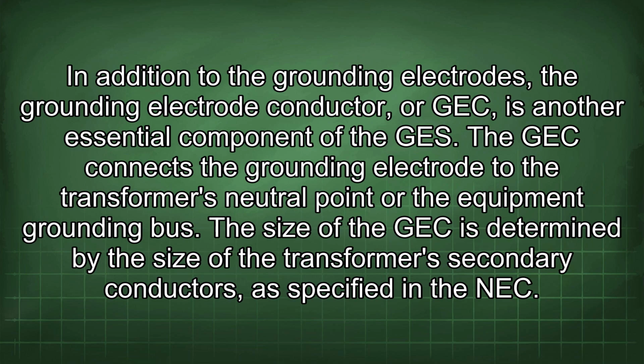In addition to the grounding electrodes, the grounding electrode conductor, or GEC, is another essential component of the GES. The GEC connects the grounding electrode to the transformer's neutral point or the equipment grounding bus. The size of the GEC is determined by the size of the transformer's secondary conductors, as specified in the NEC.